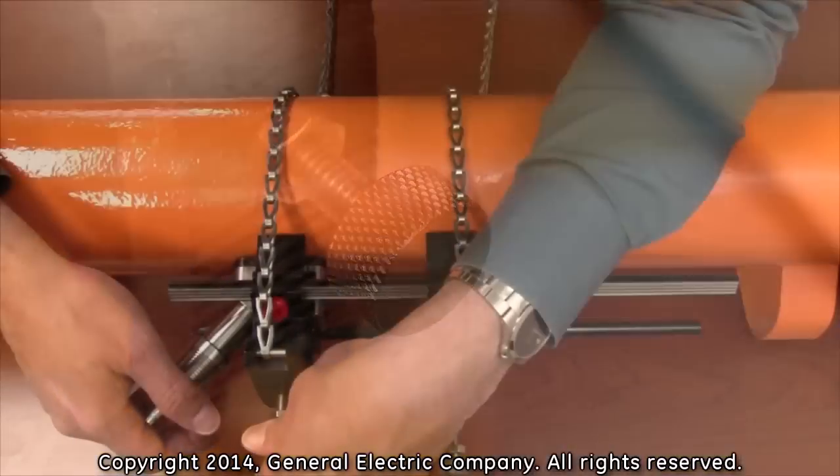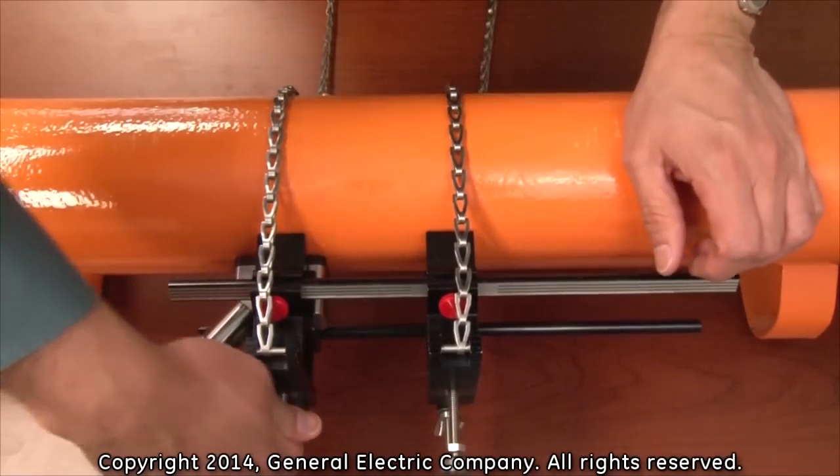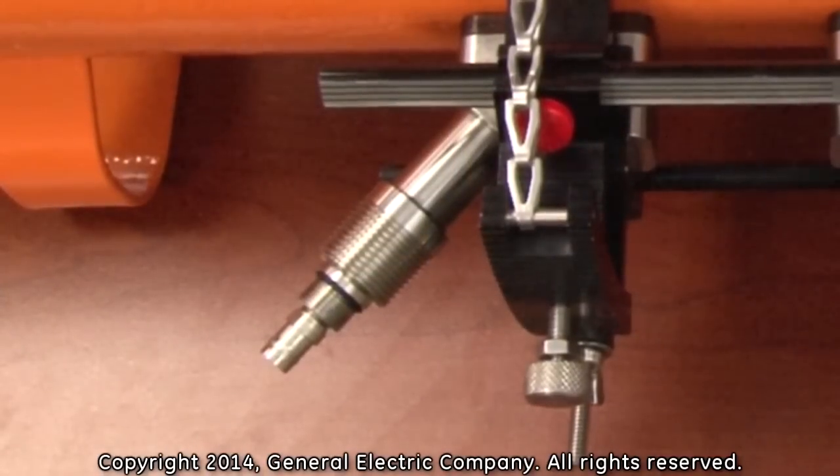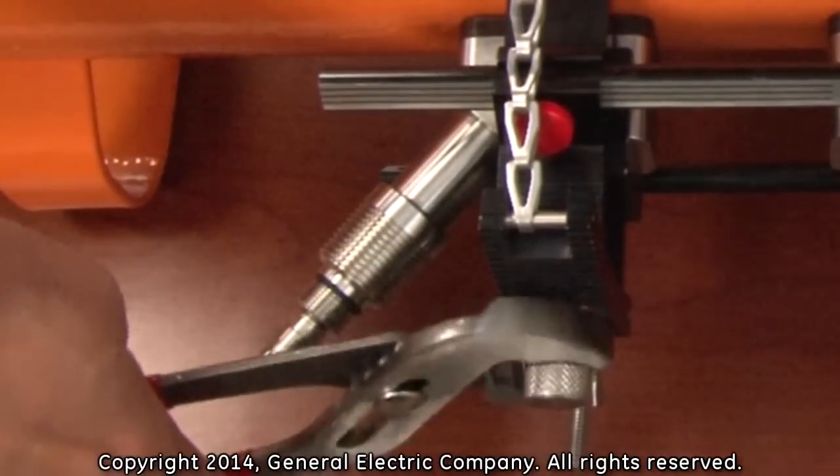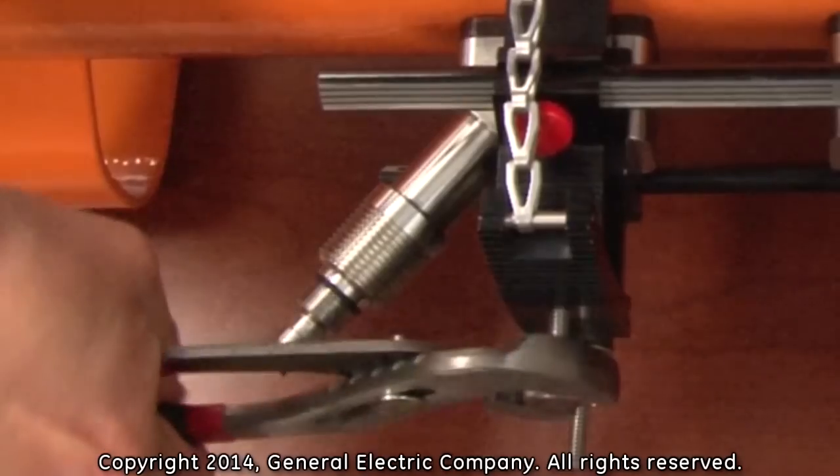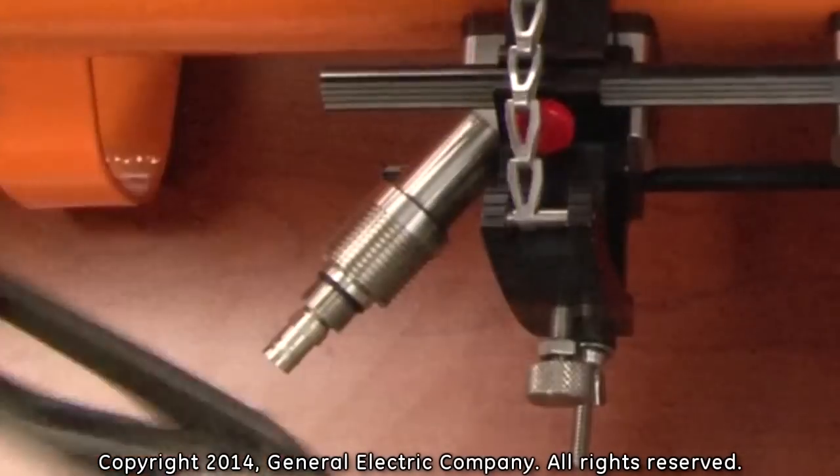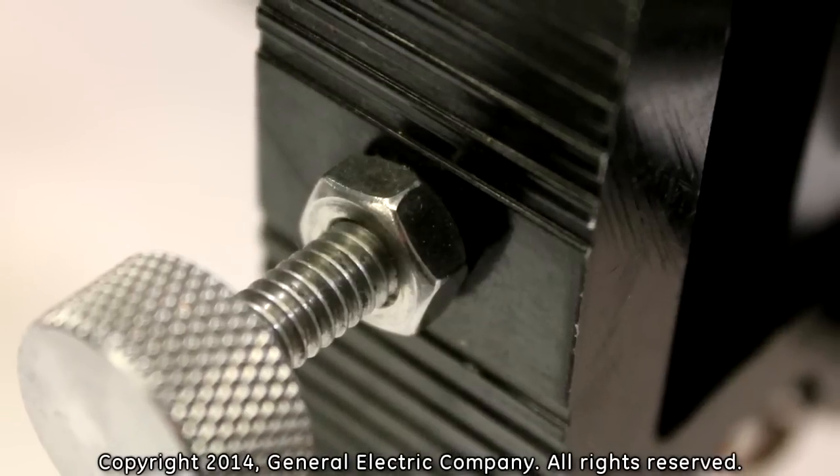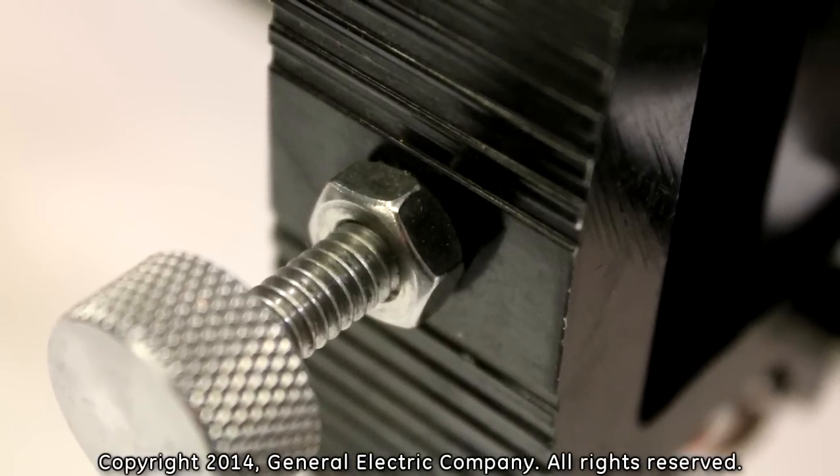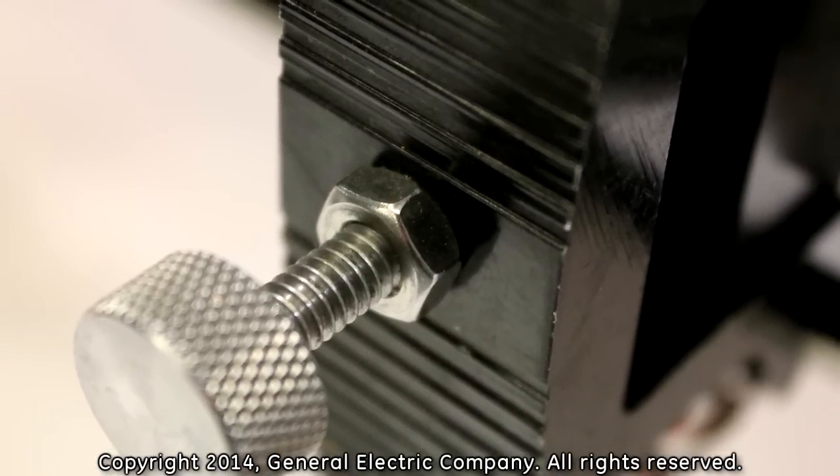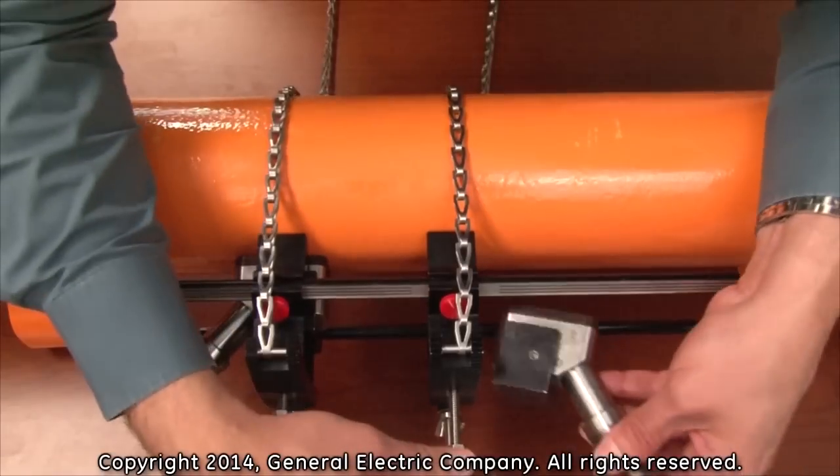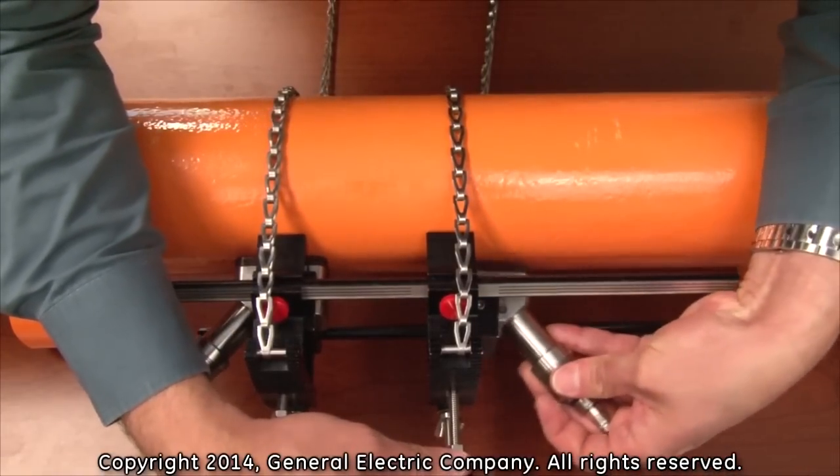Tighten the transducer securing bolt on the fixture by hand, then tighten the bolt further by only a quarter turn of a wrench. Tighten the locking nuts on the center bolts until they are firmly tightened to the top of the mounting fixture. Follow the same procedure for the installation of the other transducer.